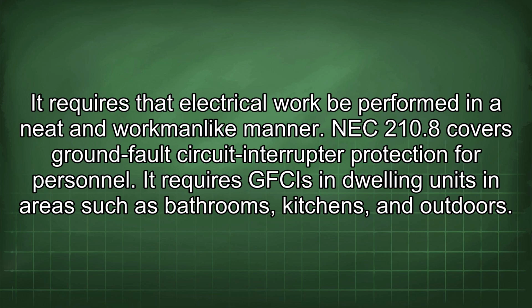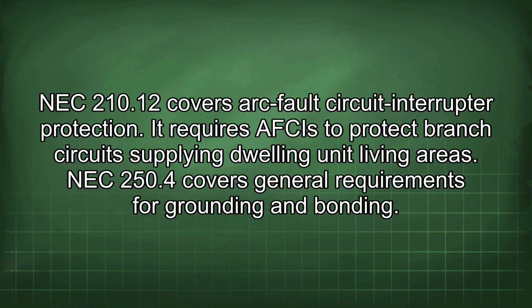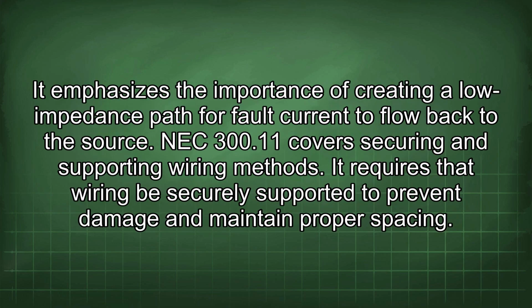NEC 210.8 covers ground fault circuit interrupter protection for personnel. It requires GFCIs in dwelling units in areas such as bathrooms, kitchens, and outdoors. NEC 210.12 covers arc fault circuit interrupter protection. It requires AFCIs to protect branch circuits supplying dwelling unit living areas. NEC 250.4 covers general requirements for grounding and bonding. It emphasizes the importance of creating a low impedance path for fault current to flow back to the source.